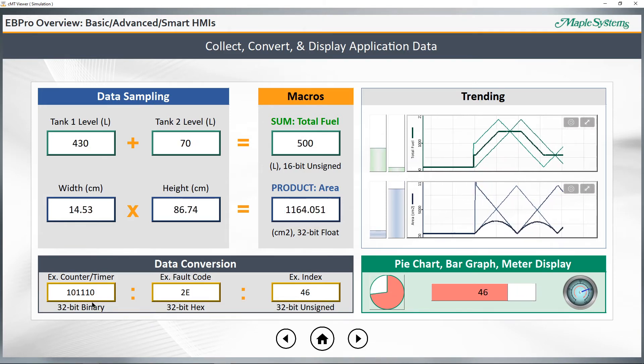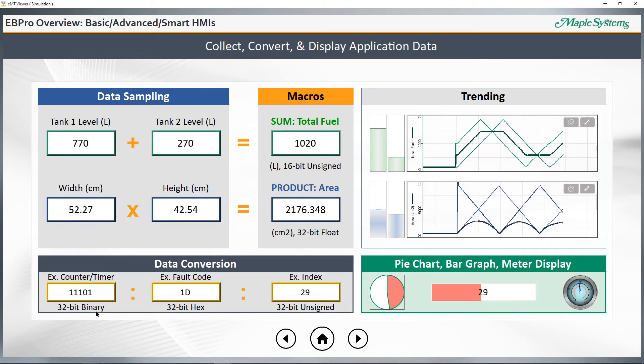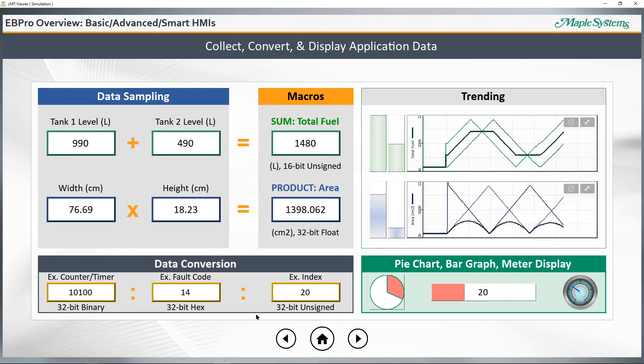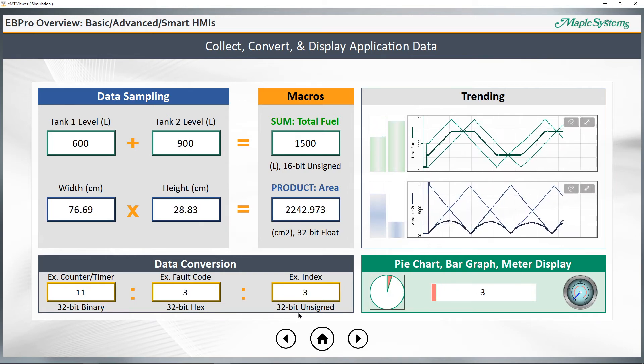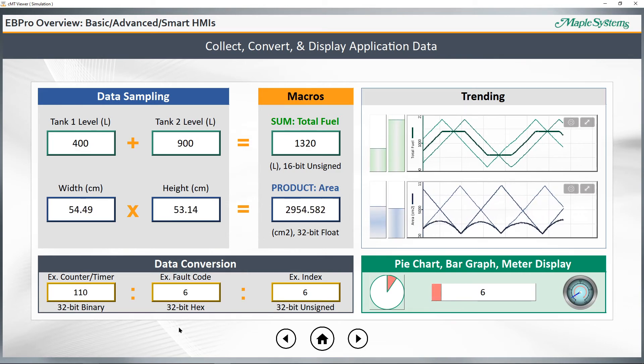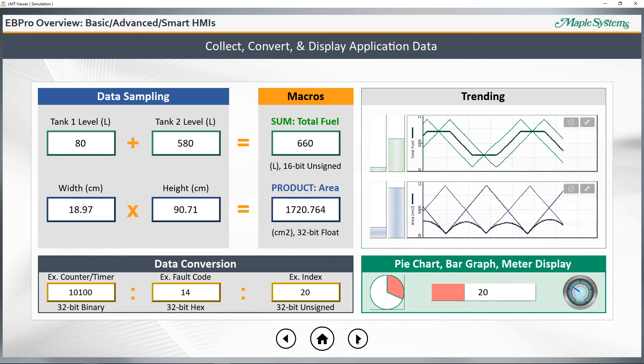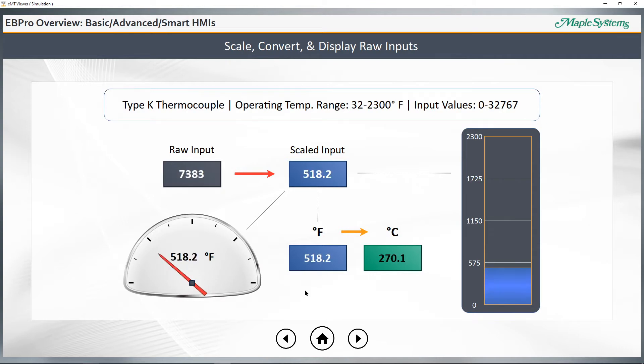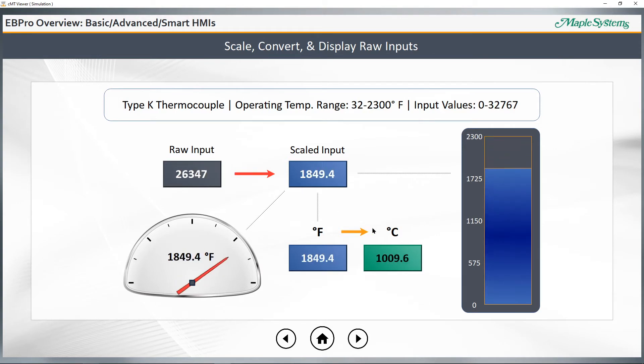You can perform data conversion of various types. For example, you might have a counter or timer in binary format, a fault code in hex format, or an index integer number. You can display any of these and convert between them, whether they're 16 or 32-bit. You may also choose to display values using pie charts and meters. You can also scale, convert, and display raw inputs with EBPro. Here's an example showing a raw analog input from a type K thermocouple — you can scale this value to show the temperature in Fahrenheit or Celsius using a numeric display, or you can use a meter or bar graph, as you see here.